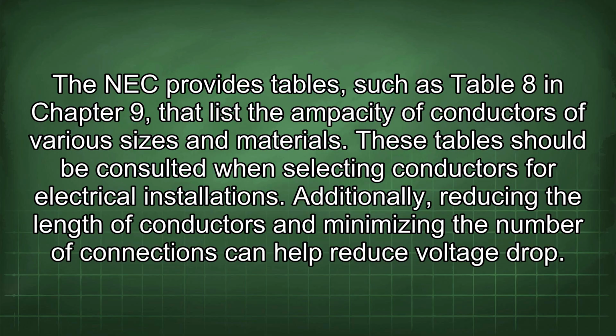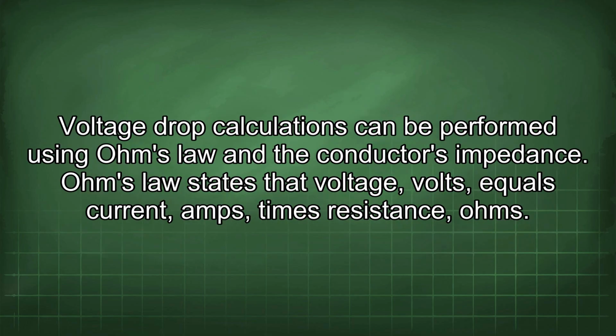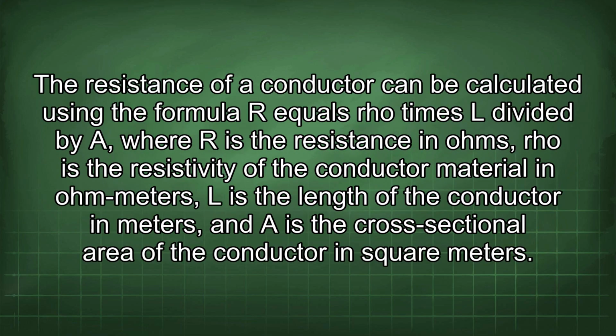Additionally, reducing the length of conductors and minimizing the number of connections can help reduce voltage drop. Voltage drop calculations can be performed using Ohm's law and the conductor's impedance. Ohm's law states that voltage in volts equals current in amps times resistance in ohms. The resistance of a conductor can be calculated using the formula R equals ρ times L divided by A, where R is the resistance in ohms, ρ is the resistivity of the conductor material in ohm meters, L is the length of the conductor in meters, and A is the cross-sectional area of the conductor in square meters.